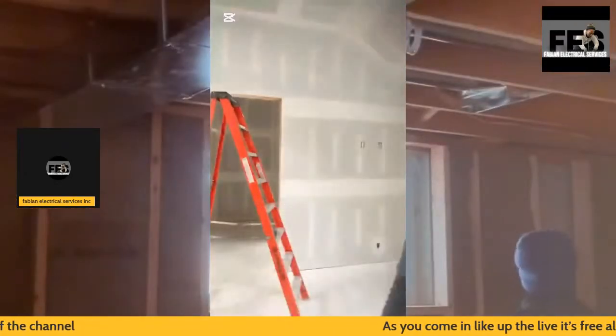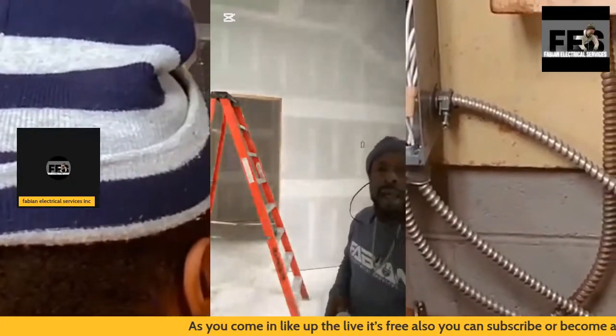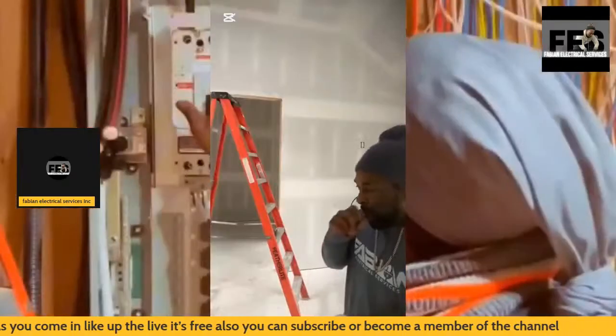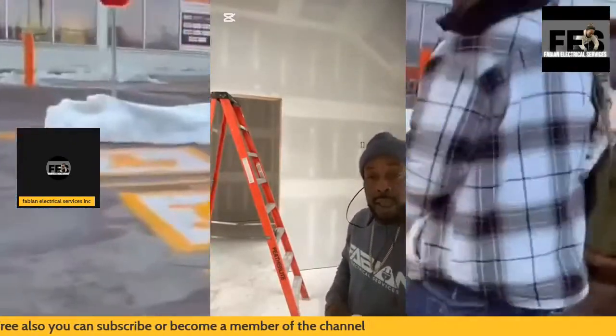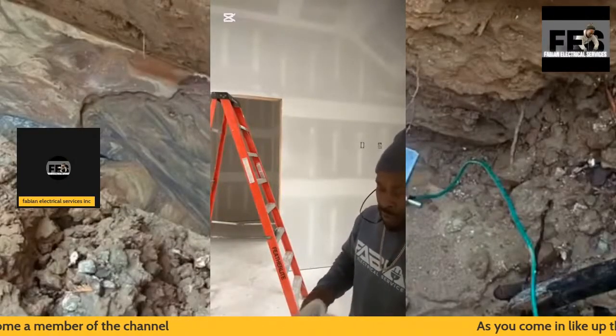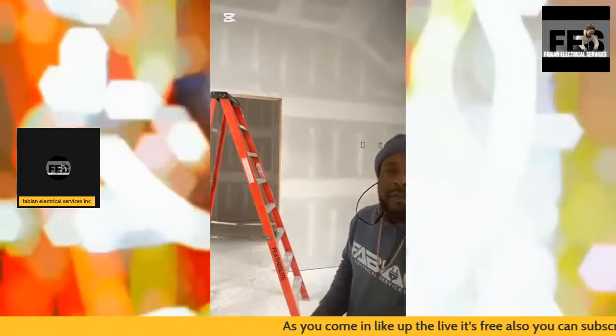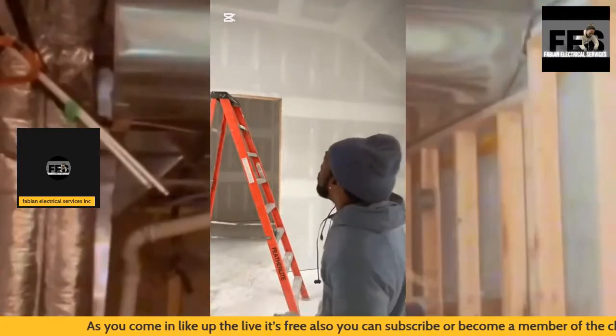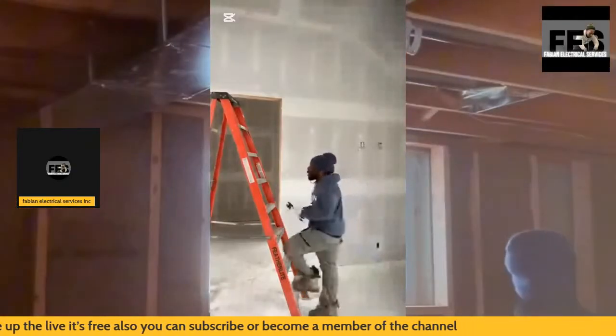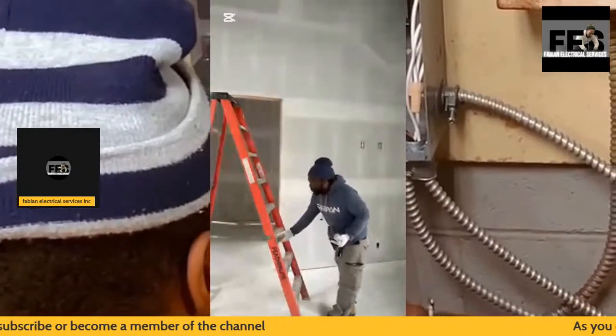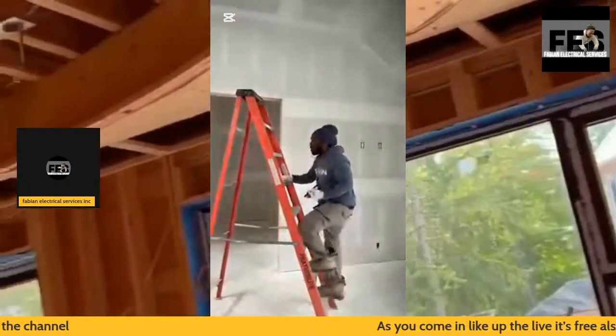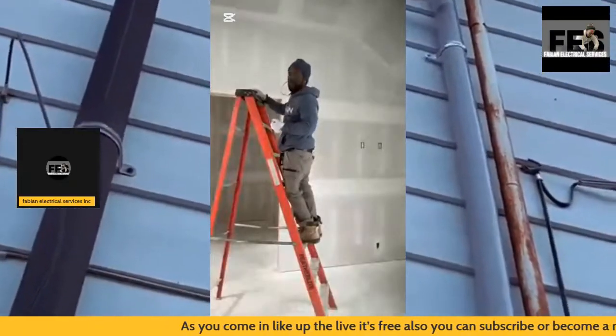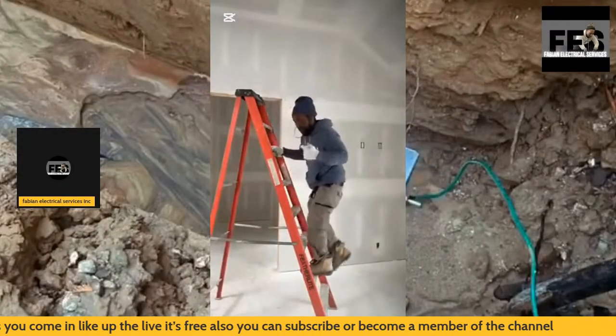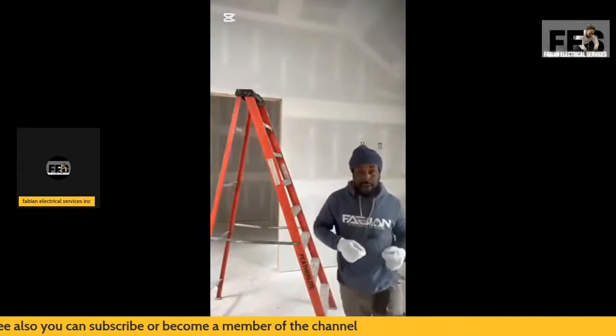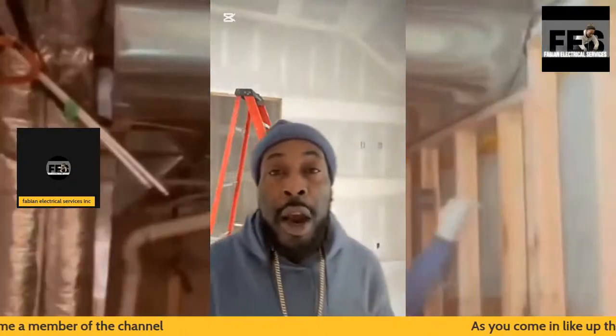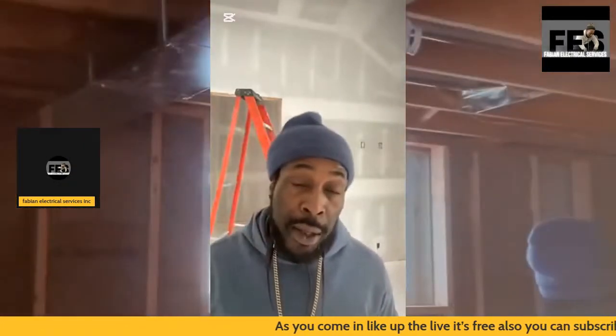So again, for all the DIYs, the electrical journeymen, the apprentices, and electricians, this one is for you. This is a video you might want to tap into to see how I normally do my electrical installation. It's also very important that once you finish your electrical installation for the lighting and smoke detectors, you label the panel with the smoke and lighting combined. That's one requirement the inspector is going to want to see at the panel, labeled in that manner.